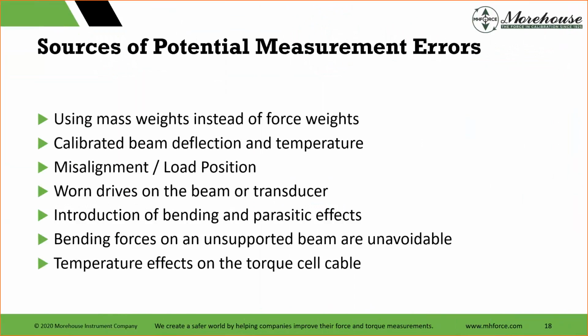So I believe why everybody's here is this section. And this section is sources of potential measurement error. And here they are. They are using mass weights instead of force weights, calibrating beam deflection and temperature, misalignment load position, worn drives on the beam or transducer, introduction of bending and parasitic effects, bending forces on an unsupported beam, those are unavoidable, and temperature effects on the torque cell cable.